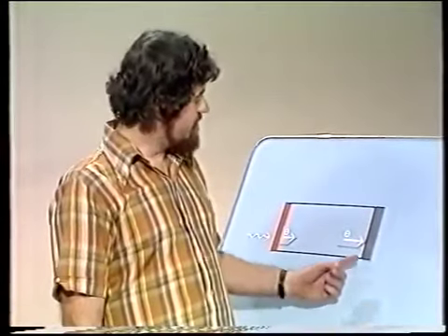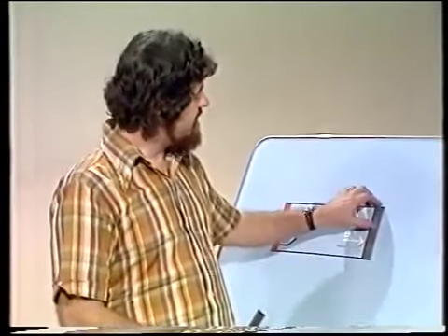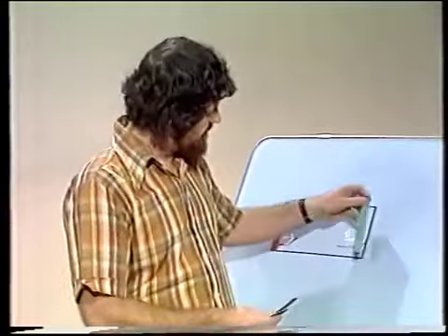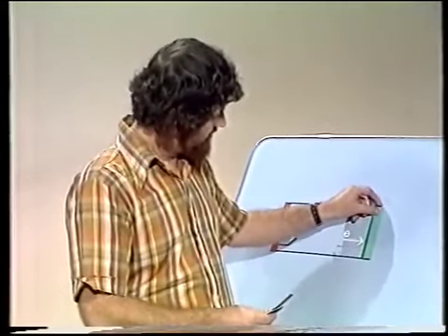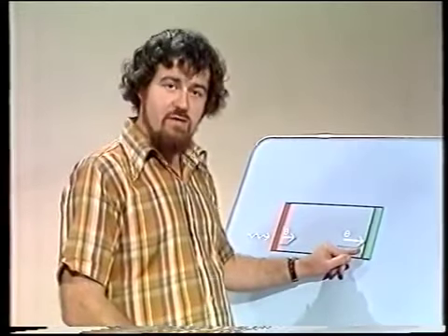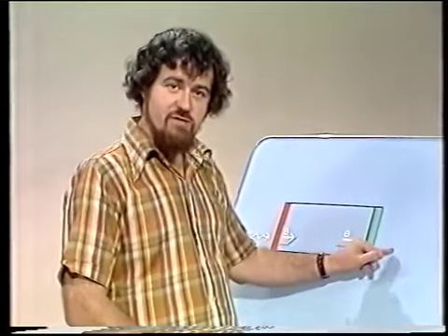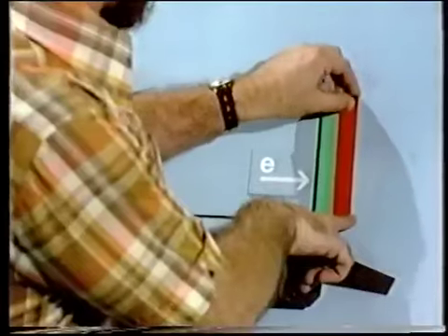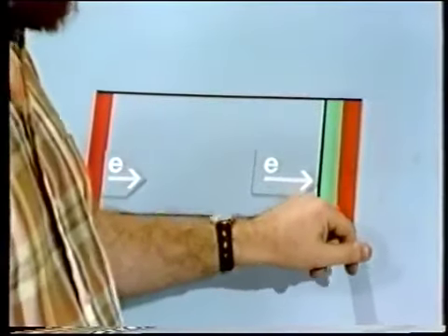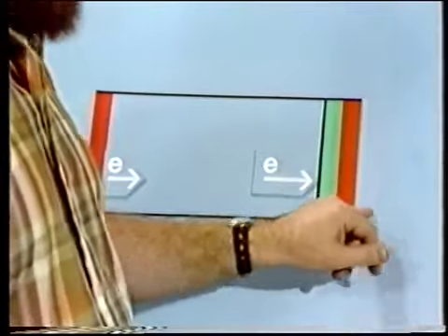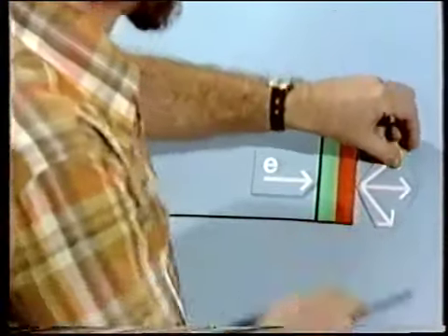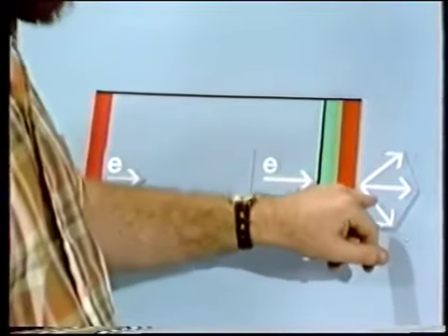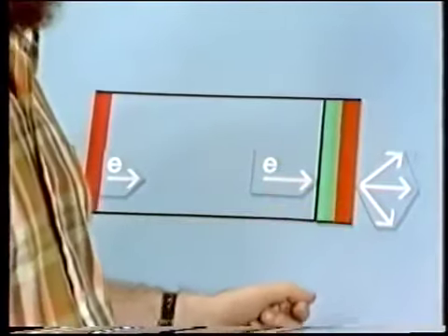Well, that's the case in which we put a photographic film here. But there is an alternative type of image intensifier. In place of photographic film, we put a substance called a phosphor, the function of which is to convert the single fast energetic electron coming in into many photons coming out. But then we put another photomaterial there, which converts those photons into electrons. So the net effect of this is to convert the single electron coming in into a whole bunch of electrons coming out. We've got electron amplification.